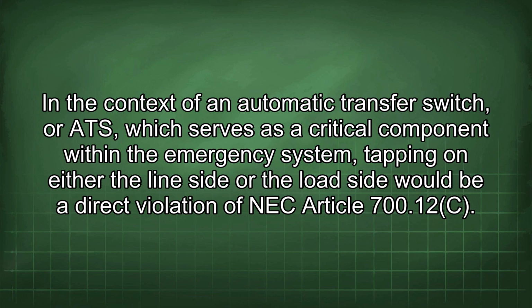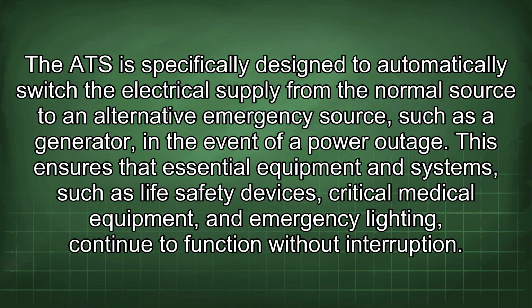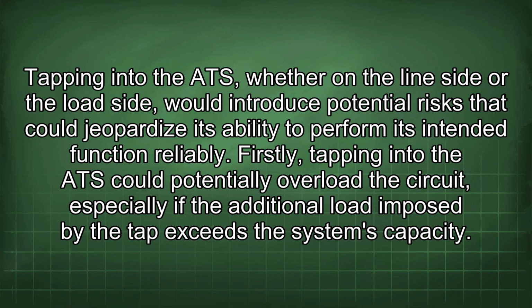In the context of an automatic transfer switch, or ATS, which serves as a critical component within the emergency system, tapping on either the line side or the load side would be a direct violation of NEC Article 700.12(C). The ATS is specifically designed to automatically switch the electrical supply from the normal source to an alternative emergency source, such as a generator, in the event of a power outage. This ensures that essential equipment and systems, such as life safety devices, critical medical equipment, and emergency lighting, continue to function without interruption. Tapping into the ATS, whether on the line side or the load side, would introduce potential risks that could jeopardize its ability to perform its intended function reliably.